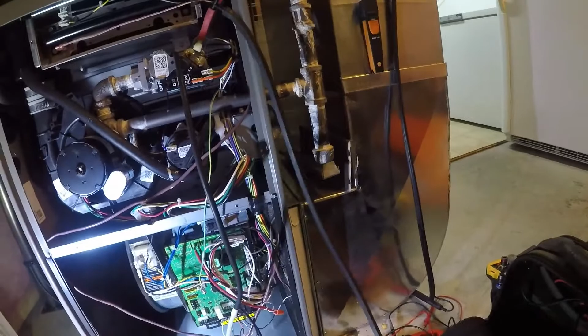On these Lennox units, this is how they want us to take the gas pressure. You want to tap into this burner box as well, stick my probe in like that, which is good enough, on the supply side. Looks like I've got a little hole here, that'll do.